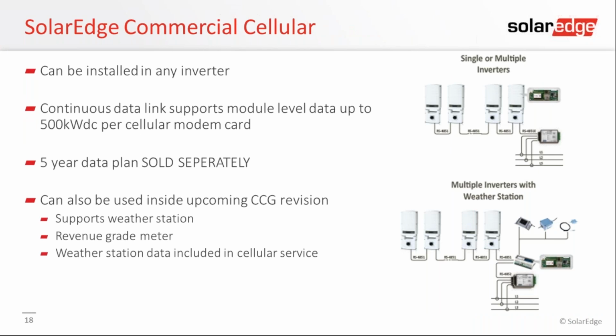For monitoring, SolarEdge now has what we call a commercial cellular kit. It's available in the US, and we're close to, if not already, bringing it into Canada, working with cell providers. With our commercial cellular GSM, we can wire up to 500 kilowatts DC to one cellular card. The modem installs directly into the inverter, and you daisy chain RS-485 between inverters, so you don't have to integrate your inverter communications into the building's network.